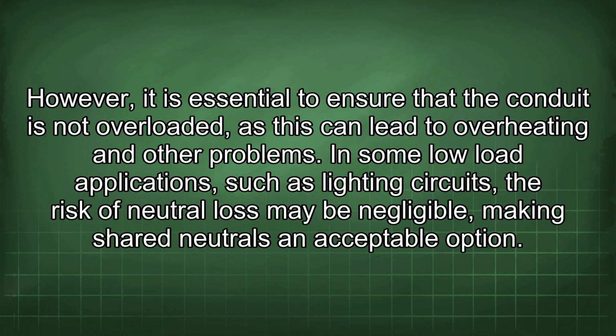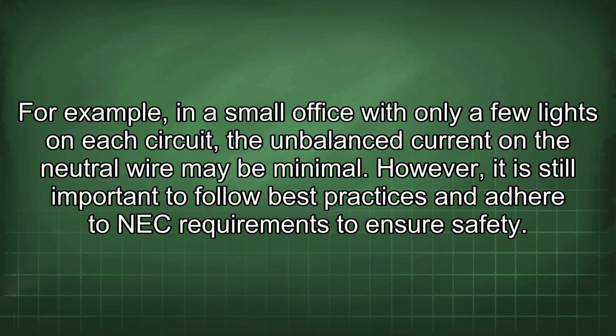However, it is essential to ensure that the conduit is not overloaded, as this can lead to overheating and other problems. In some low-load applications, such as lighting circuits, the risk of neutral loss may be negligible, making shared neutrals an acceptable option. For example, in a small office with only a few lights on each circuit, the unbalanced current in the neutral wire may be minimal. However, it is still important to follow best practices and adhere to NEC requirements to ensure safety.